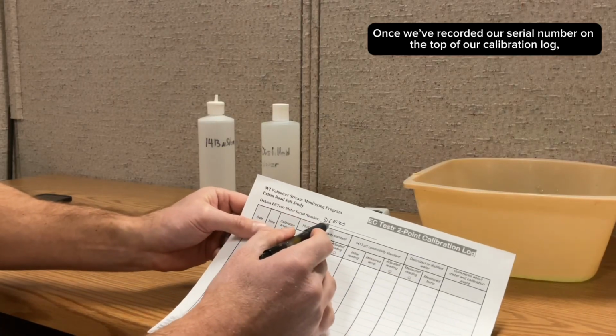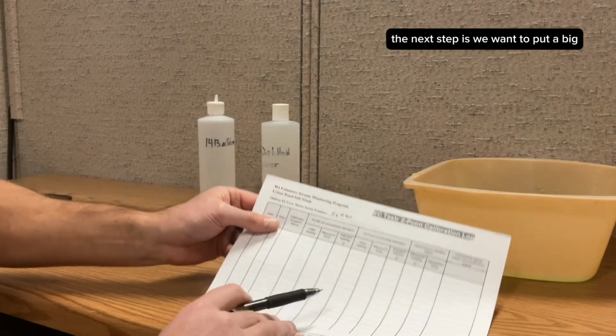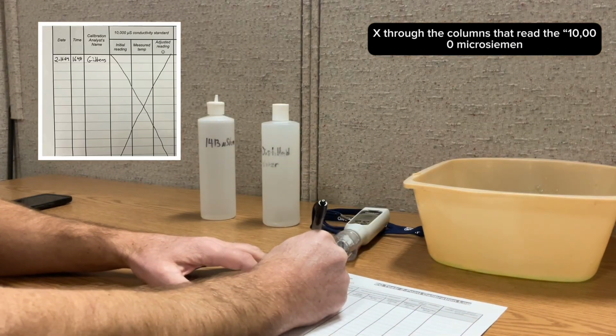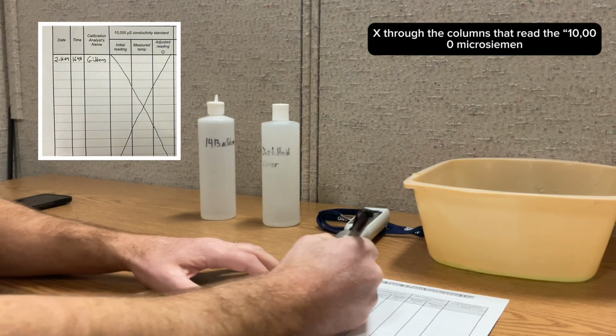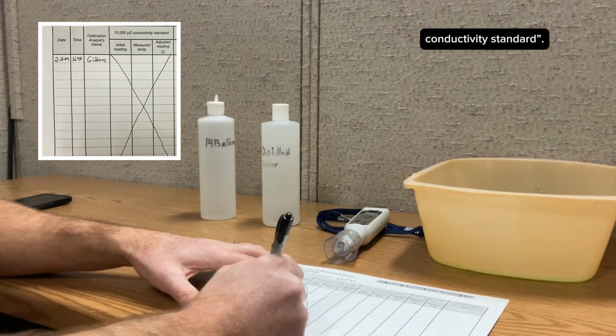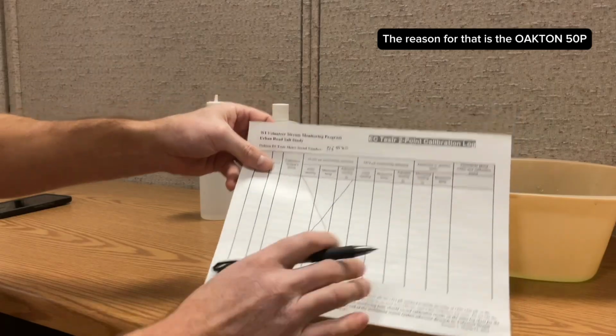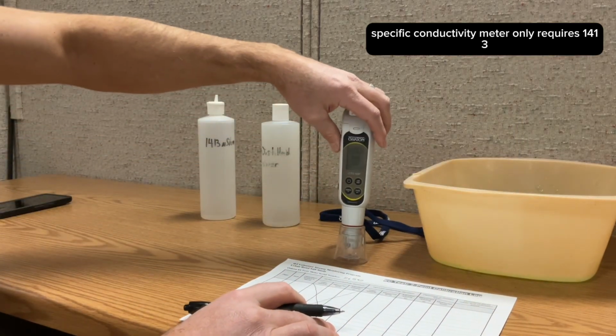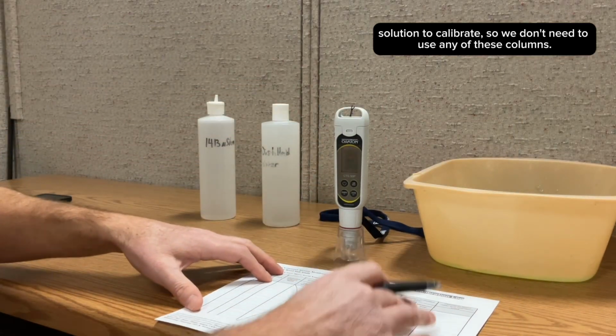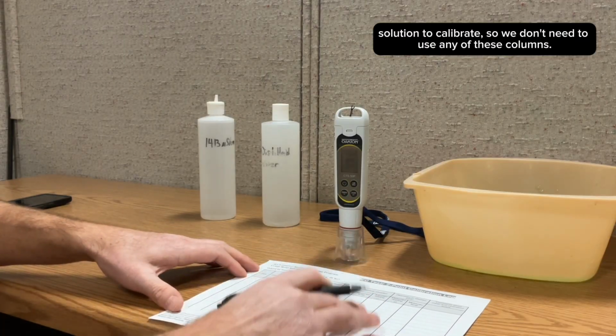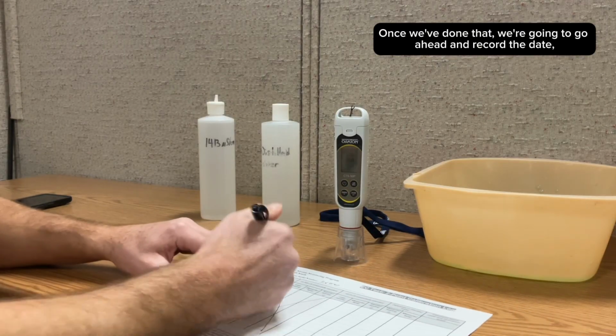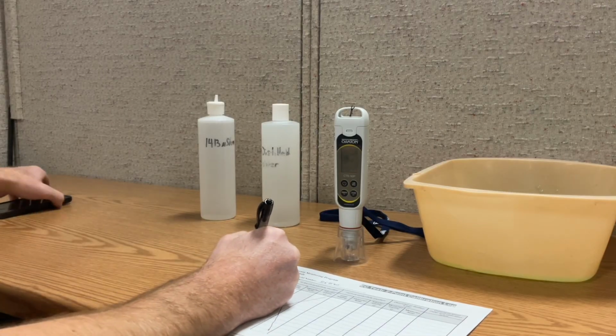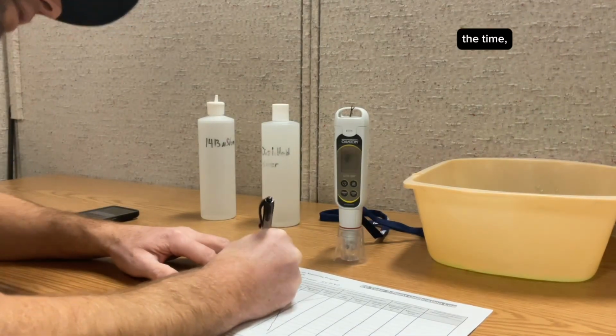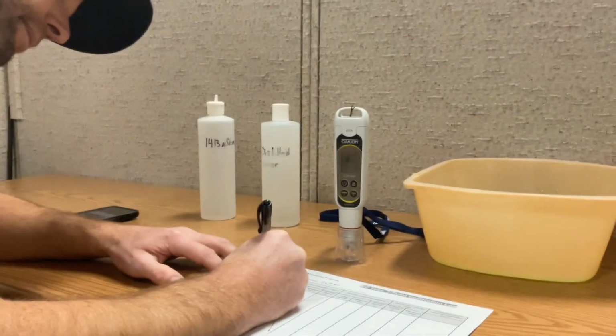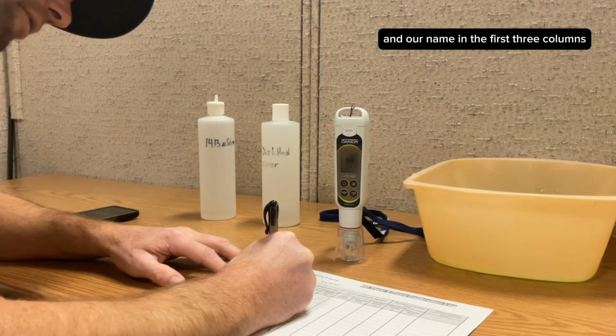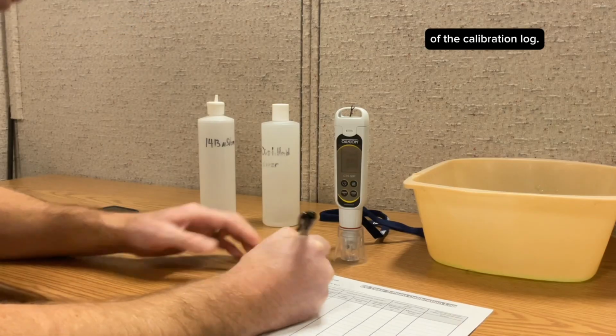Once we've recorded our serial number on the top of our calibration log, the next step is we want to put a big X through the columns that read the 10,000 microsiemens conductivity standard. The reason for that is the OAKTON 50P specific conductivity meter only requires 1413 solution to calibrate, so we don't need to use any of these columns. Once we've done that, we're going to go ahead and record the date, the time, and our name in the first three columns of the calibration log.